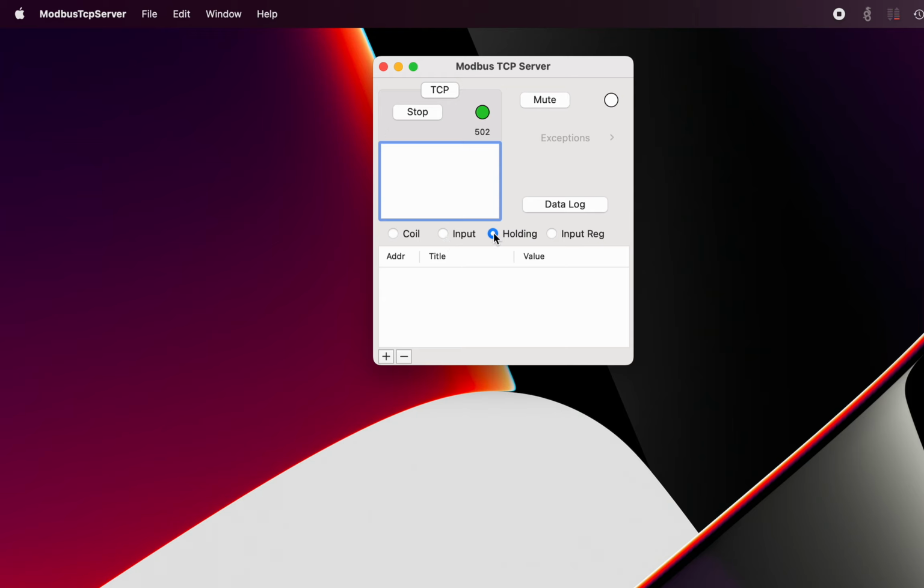Modbus supports a coil memory, which is classically outputs, and input memories, and they're digital, so they're only a 0 or 1. We have a digital input, 0 or 1. We've got a holding register, which is a multi-bit register. In Modbus terms, a single register is 16 bits wide. And we have an input register as well. These are classically used for analog inputs, for example, to be read in the classic Modbus system. Holding registers are probably the most popular.